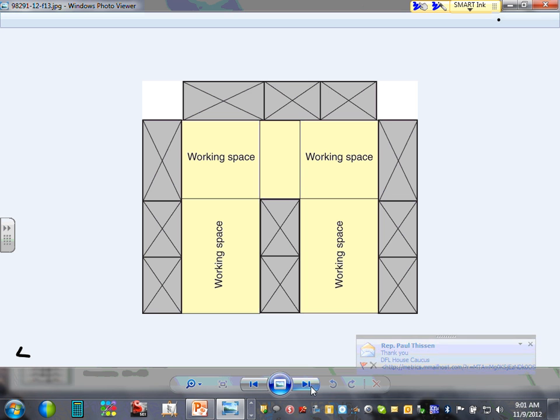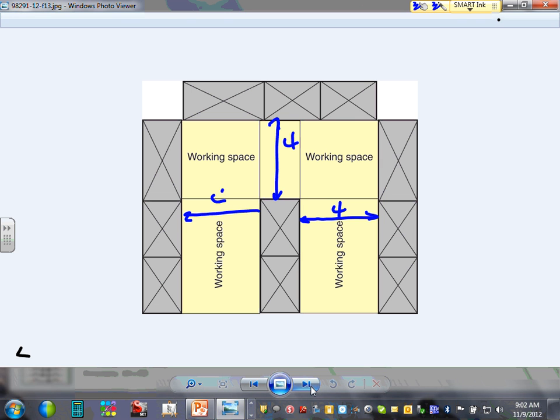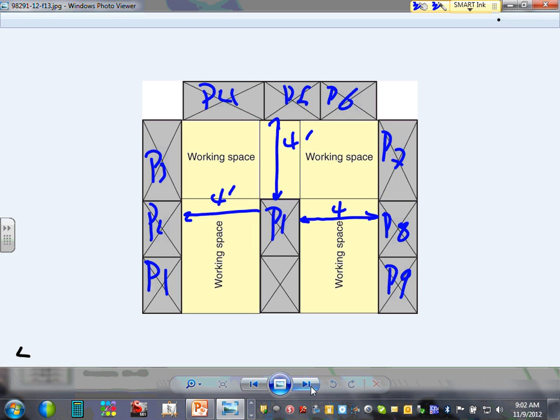Imagine all these are panels. And imagine here's 4 feet between face to face here. If I allow 4 feet here, and allow 4 feet here, and allow 4 feet here, am I covered for almost all the conditions? Almost all the conditions except one condition. So that's what most engineers do, guys. When you start the design, they make it 4 foot. Here's my panel. So this is starting from here. This is panel 1, panel 2, panel 3, panel 4, panel 5, panel 6, panel 7, panel 8, panel 9. 9 panels. Panel 10, panel 11.